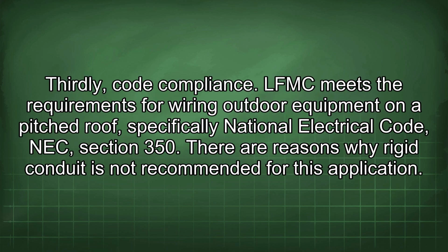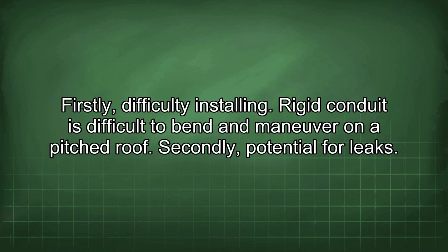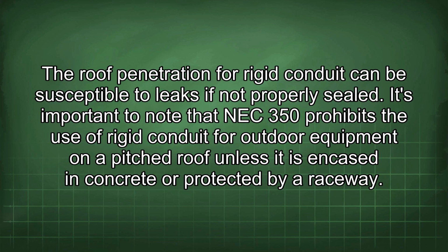Thirdly, code compliance. LFMC meets the requirements for wiring outdoor equipment on a pitched roof, specifically National Electrical Code, NEC, Section 350. There are reasons why rigid conduit is not recommended for this application. Firstly, difficulty installing. Rigid conduit is difficult to bend and maneuver on a pitched roof. Secondly, potential for leaks. The roof penetration for rigid conduit can be susceptible to leaks if not properly sealed.